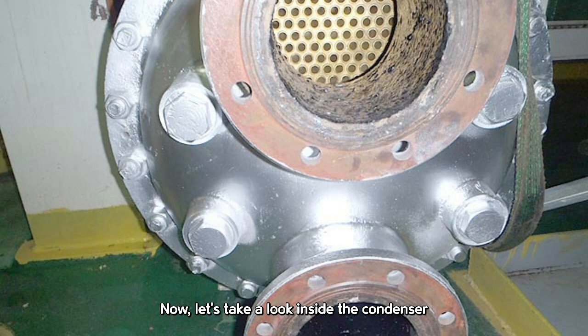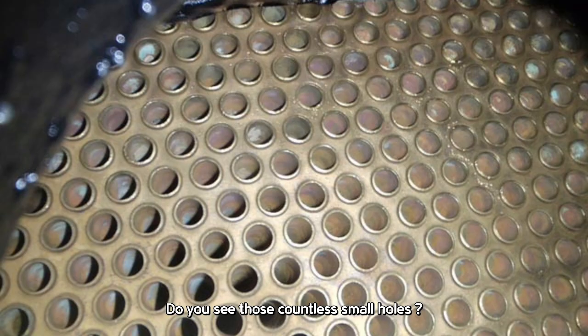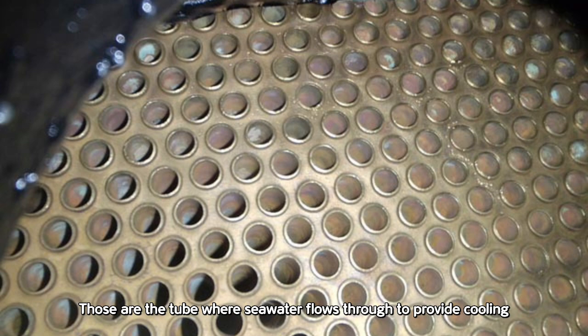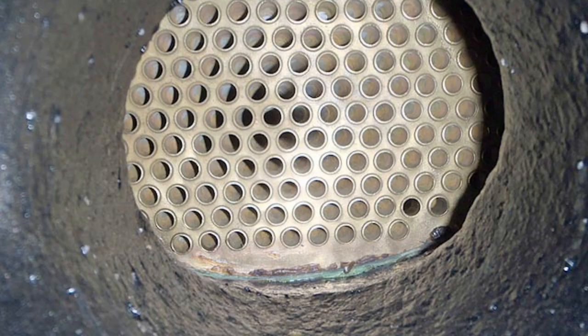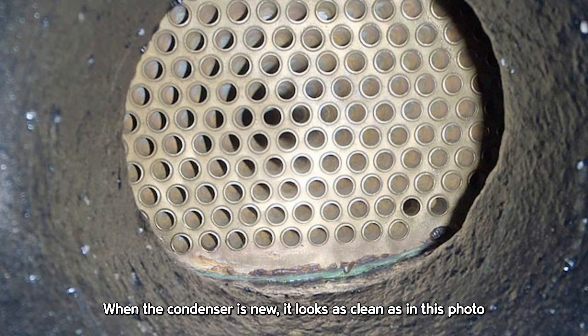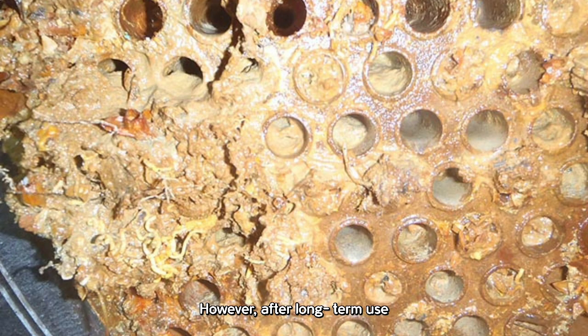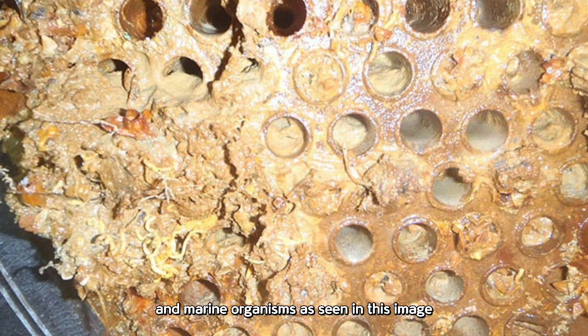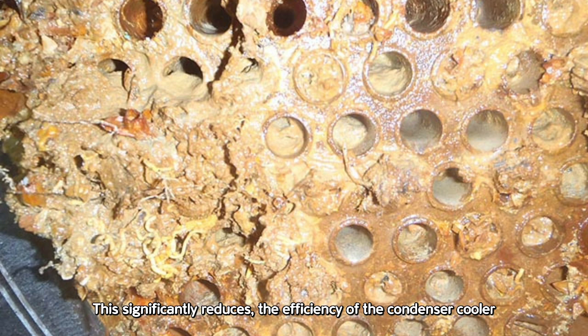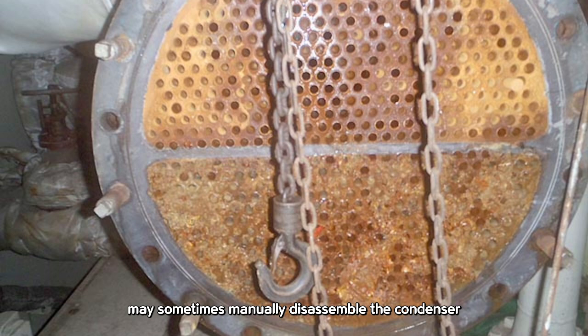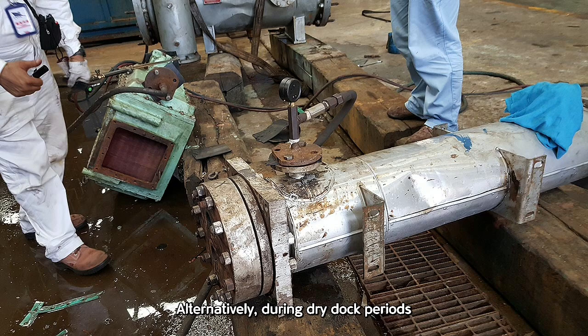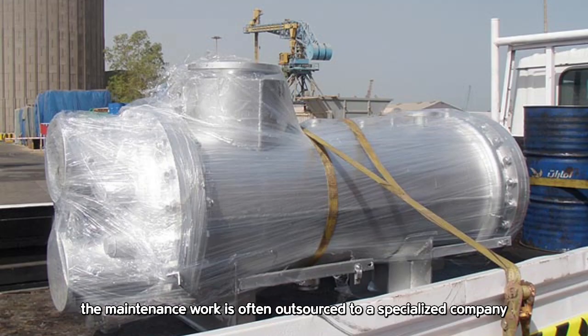Now, let's take a look inside the condenser. Do you see those countless small holes? Those are the tubes where seawater flows through to provide cooling. As the cooling seawater passes through these tubes, it cools the high-temperature steam flowing around the outside of the tubes. When the condenser is new, it looks as clean as in this photo. However, after long-term use, many of the tubes can become clogged with mud and marine organisms. This significantly reduces the efficiency of the condenser cooler. In such cases, ship crew members may sometimes manually disassemble the condenser and clean the clogged tubes themselves. Alternatively, during dry dock periods, the maintenance work is often outsourced to a specialized company for thorough overhaul.